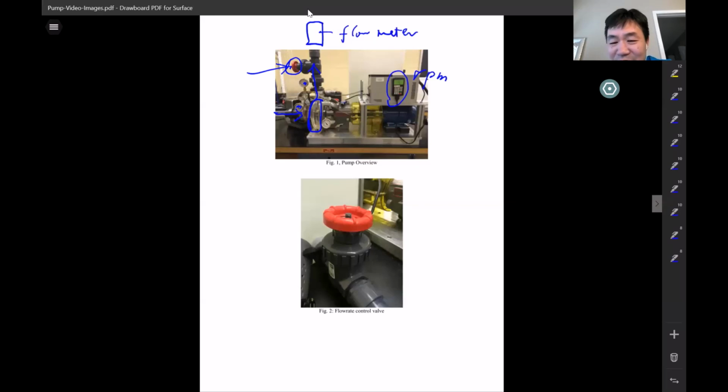But next time when you do it, you actually forget where exactly the valve opening is. You cannot track back to the second time when you measure the second pump curve, or trace back to the original 6 openings you measured for the first pump. This is manual, it's not digital. So if you measure the two pump curves separately, you cannot verify the affinity law. Affinity law can only be verified in the same system, same valve opening.